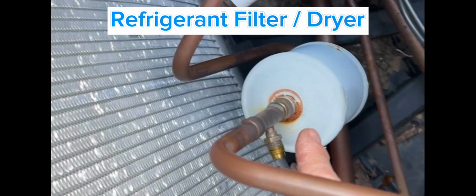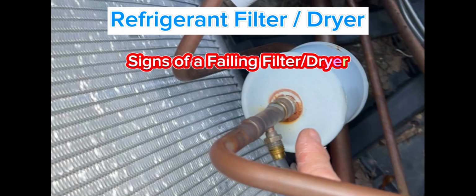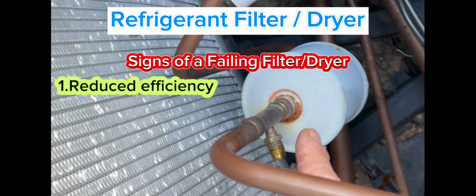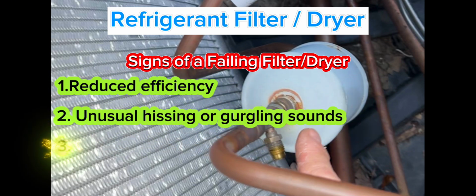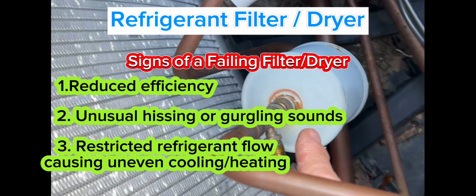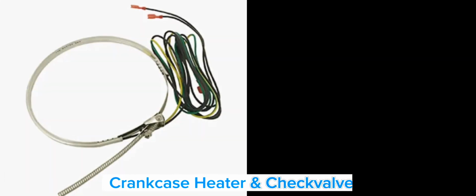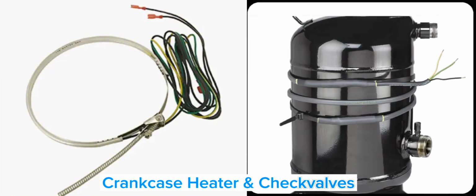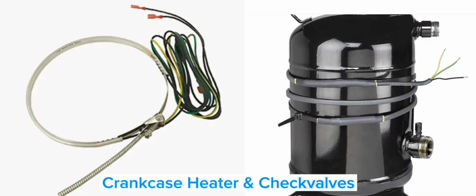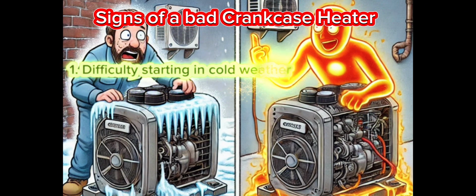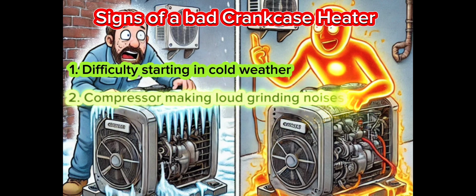This small but crucial component removes moisture and debris from the refrigerant, preventing contamination that could clog your system or damage internal components. In colder climates, compressors need a crankcase heater to keep refrigerant oil from thickening and damaging internal components upon startup. If this little heater fails, your compressor could struggle to start, or worse, seize up completely.